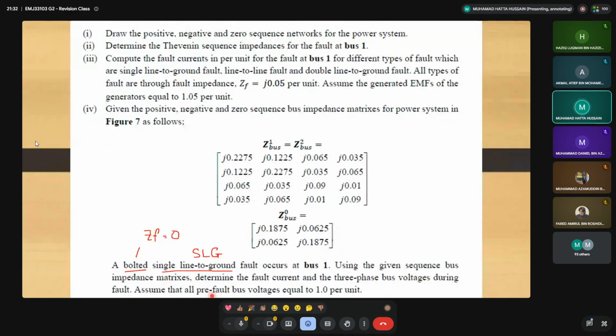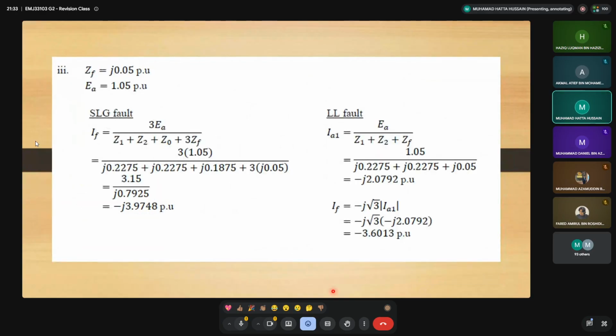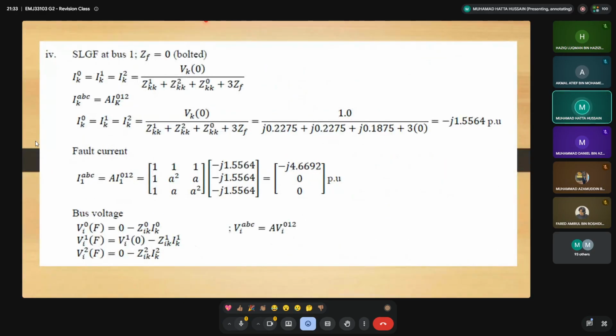Assume that all pre-fault bus voltages, which means before the fault occurs, equal 1.0 per unit. For this one, you need to refer to this matrix here for the positive sequence, negative sequence, and zero sequence bus impedance. Okay, how to solve this one? From the given question, SLG, single line to ground fault, you need to memorize, or refer to, the basic formula for the single line to ground fault.